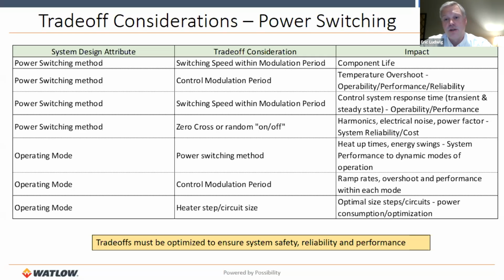So if you have a very long modulation period, you may not be able to control your system to a precise temperature. Shorter modulation periods allow you to switch that power on and off faster and have a better response to transients or other items that may impact the temperature of your system. Your operating mode comes into play as well.